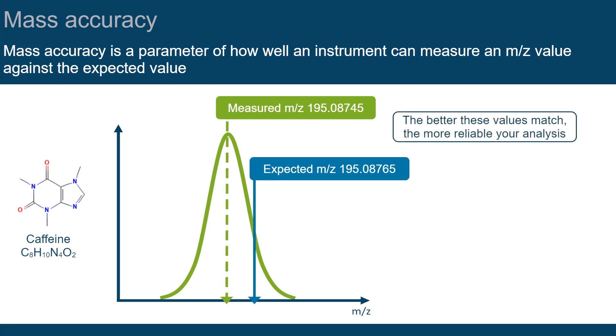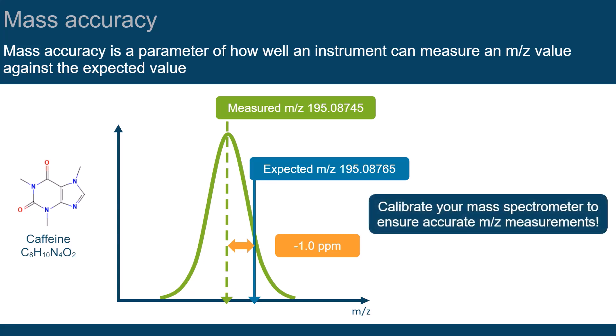The better these values match, the more reliable is the result of your analysis. The value is usually calculated and reported in ppm. Performing an accurate mass calibration of the mass spectrometer ensures that you make accurate M over Z ratio measurements.